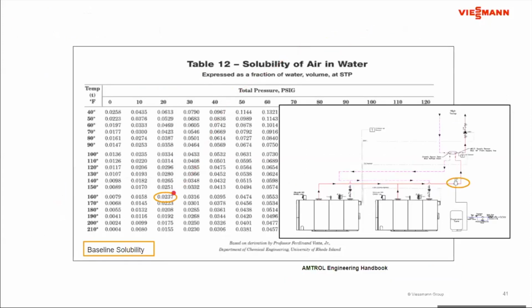Jump back in here. So that's my baseline point right here. But again, if I said the air separator could be here, if I'm mixing, all of a sudden my 160-degree water can become 150. The solubility goes up. There's air, I don't get all the air that I possibly can out. I can get all the air that I can out here, but when I'm down here, there's air that comes out of solution and then goes back into solution. So I'm not pulling all the air out as possible here based on temperature. But if this was at the top of the building, I may only be at 10 psi versus 20. All of a sudden, the 0.0237 becomes a 0.0158, or the 2.37% saturation point becomes a 1.58% saturation point. Air comes out of solution right here.